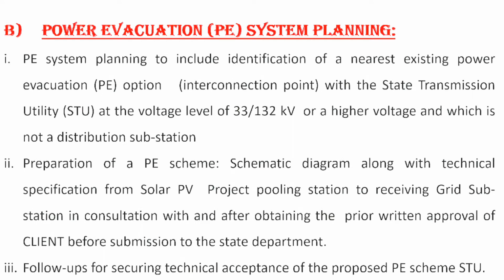Then comes power evacuation - the land should be near the substation. And this evacuation substation, whether it is 11 kV or 33 kV or 132 kV - accordingly you are going to design your project also, because you will need the output to evacuate the supply as per the rating of the substation.